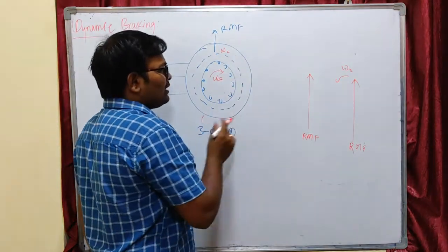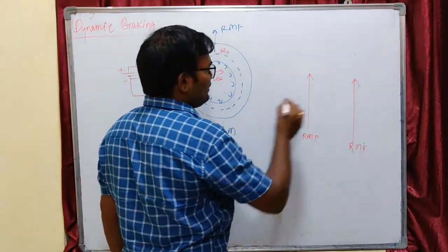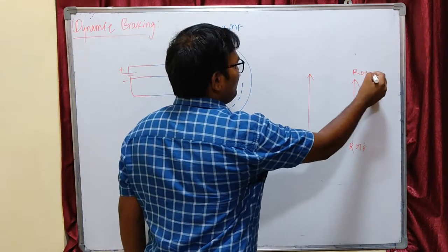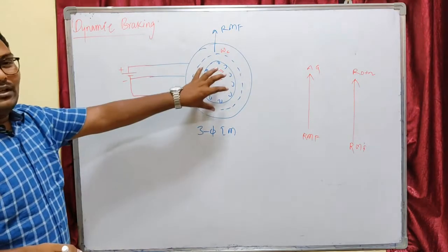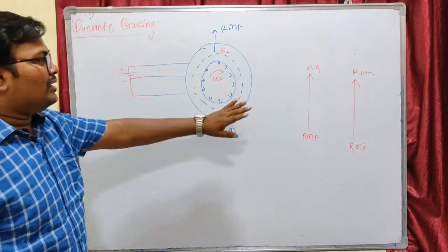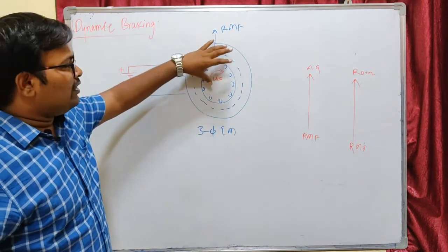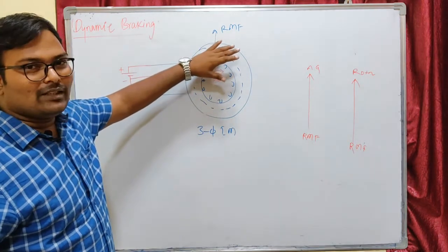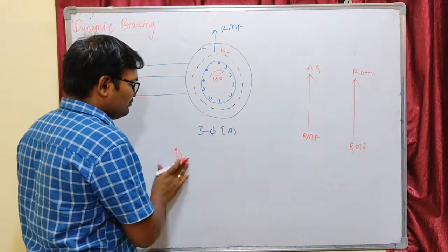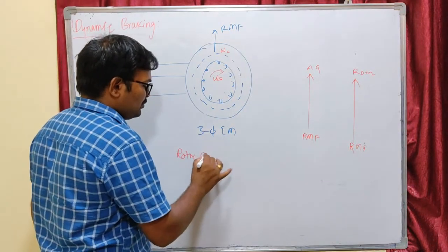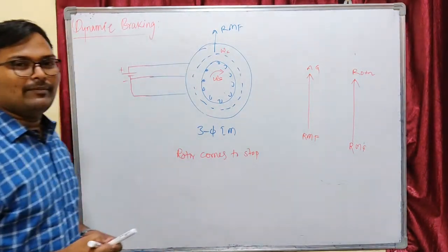As the DC flux cuts with the rotor conductors, there will be a unidirectional magnetic field produced in the rotor also — this is in the rotor, this is in the air gap. This will bring the rotor to zero speed. Because the rotor was rotating due to the interaction between the air gap and rotor rotating magnetic fields, now there is no interaction between them and no relative speed, so the rotor comes to a stop. This is dynamic braking.